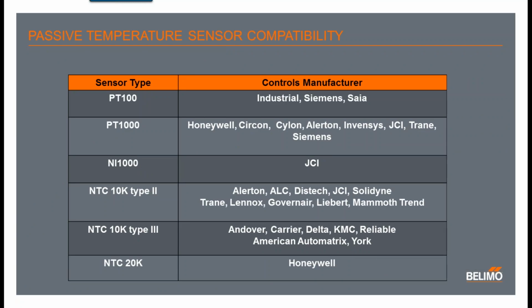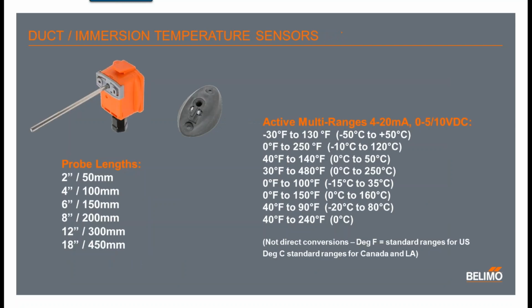For passive NTC, PTC sensors, we have selected the major sensors to be compatible with the Americas market. Those sensors are PT100, PT1000, Nickel 1000, 10K2, 10K3 and NTC 20K. Our duct sensors come in various lengths from 2-inch to 18-inch. We use exactly the same product for both duct and immersion sensors, which reduces your product selection and reduces your inventory levels. Again, we have various different mounting options, mounting brackets for standard, uneven, or even round ducts.